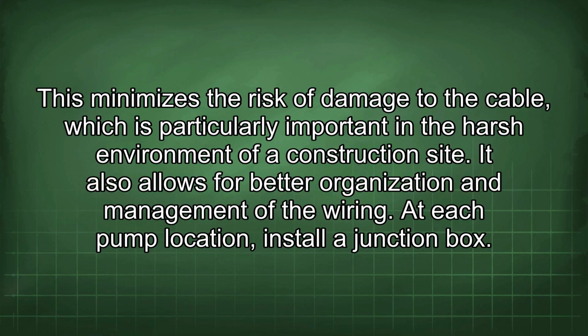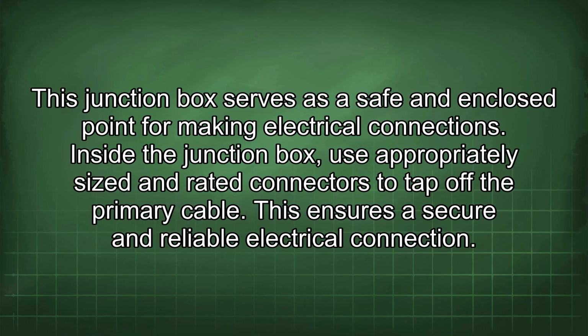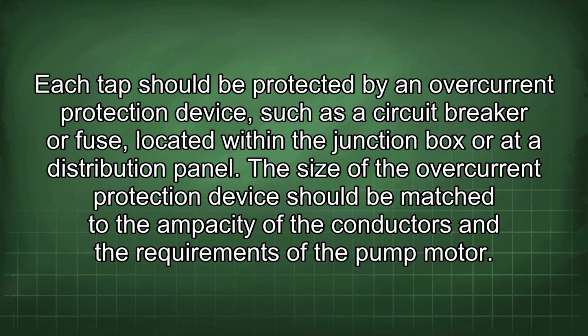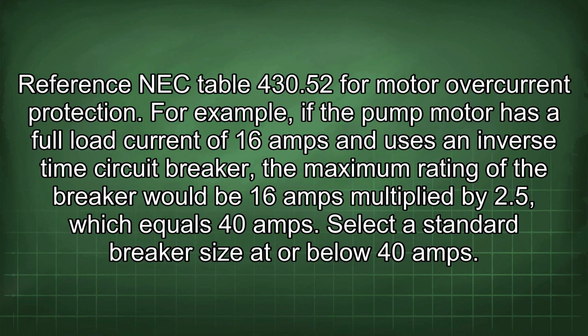At each pump location, install a junction box. This junction box serves as a safe and enclosed point for making electrical connections. Inside the junction box, use appropriately sized and rated connectors to tap off the primary cable. This ensures a secure and reliable electrical connection. Each tap should be protected by an overcurrent protection device, such as a circuit breaker or fuse, located within the junction box or at a distribution panel. The size of the overcurrent protection device should be matched to the ampacity of the conductors and the requirements of the pump motor. Reference NEC Table 430.52 for motor overcurrent protection.